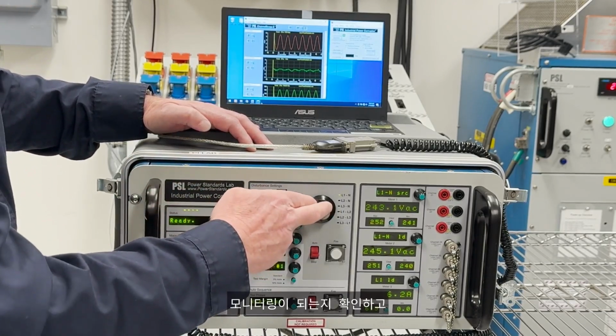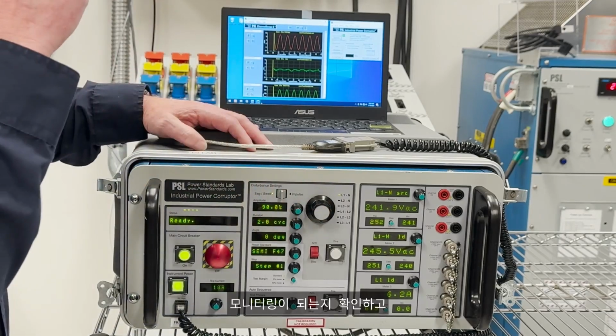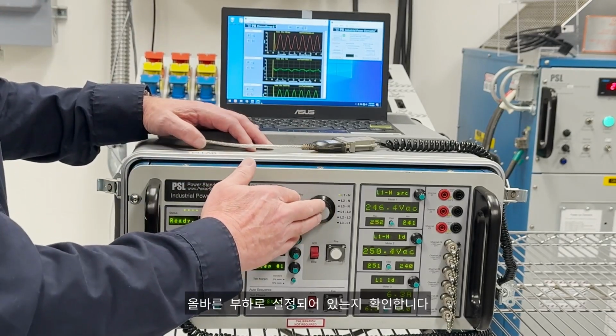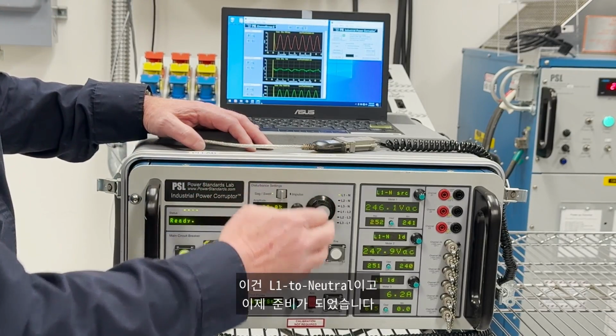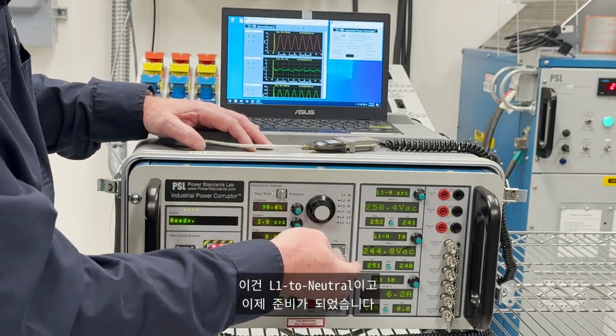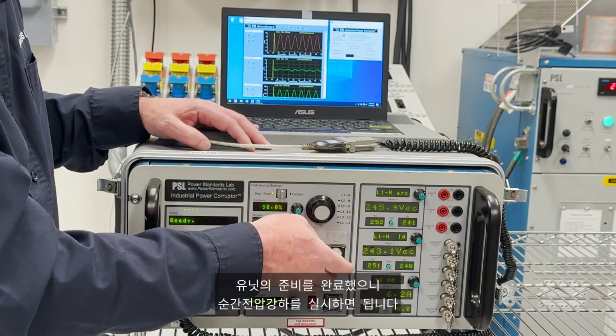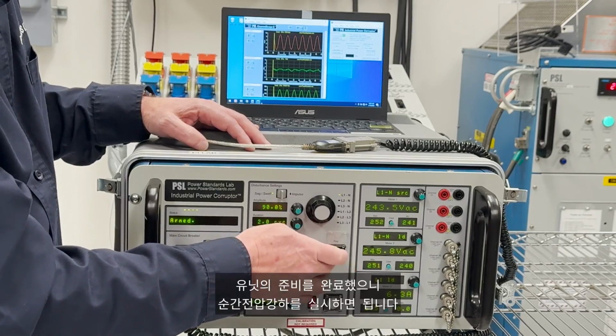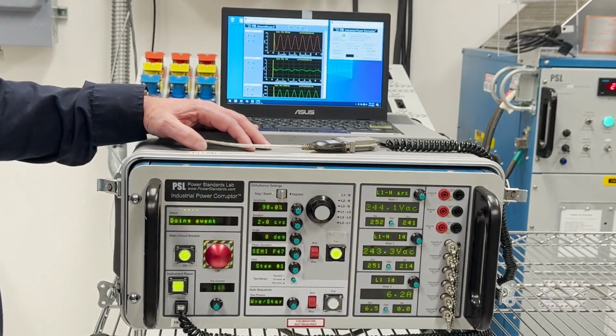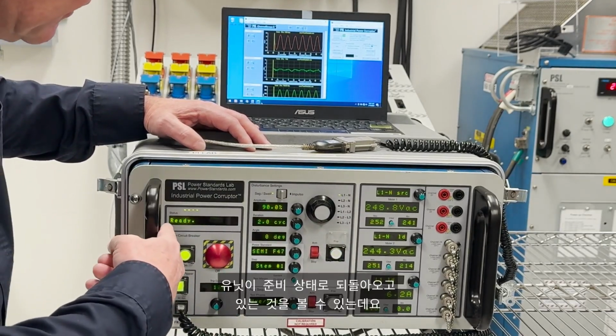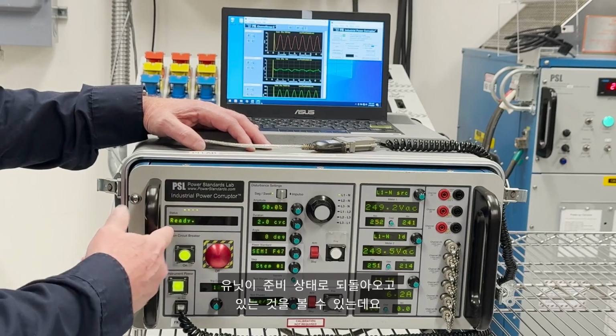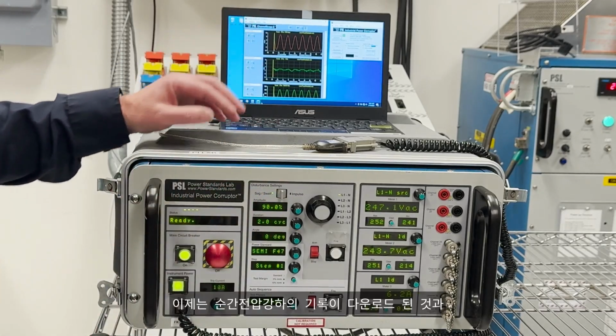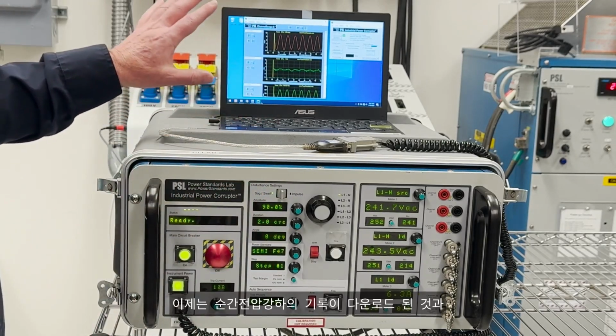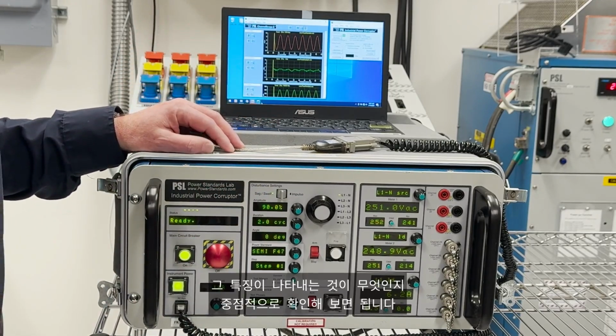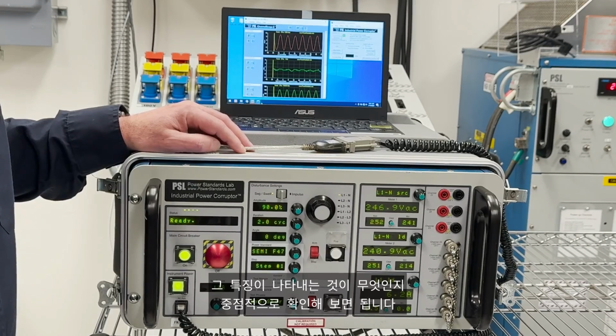Let's make sure that we're monitoring and we are set to the correct load. So this is line 1 to neutral, and then we're ready to go. We can arm the unit and then fire. And you can see that the unit returns to ready, it's recorded, and then we need to focus on the download and the characteristics of this sag and what it shows.